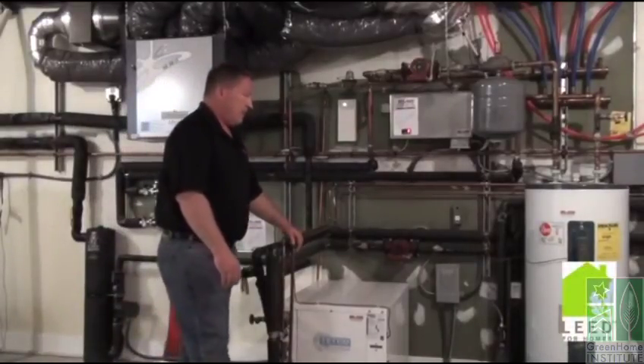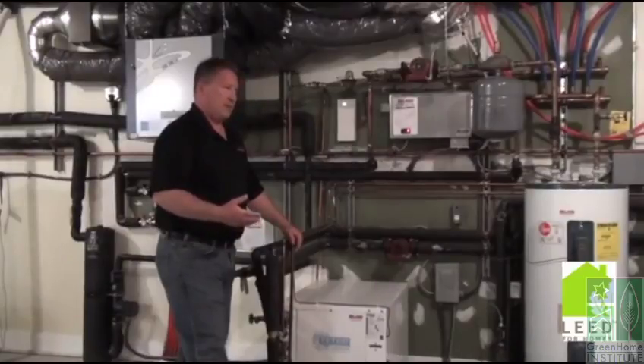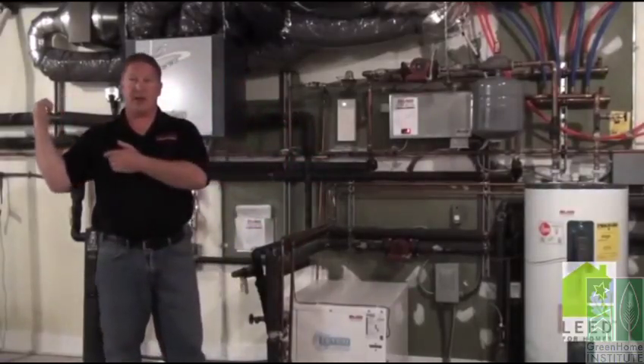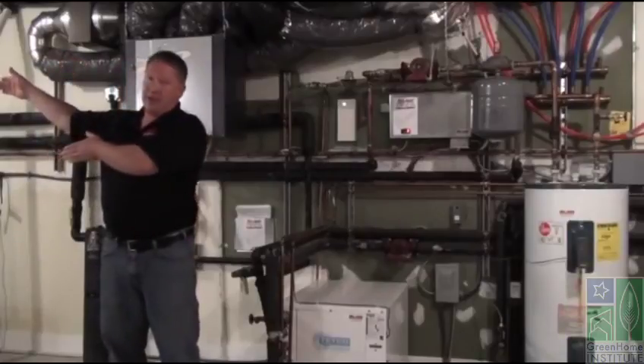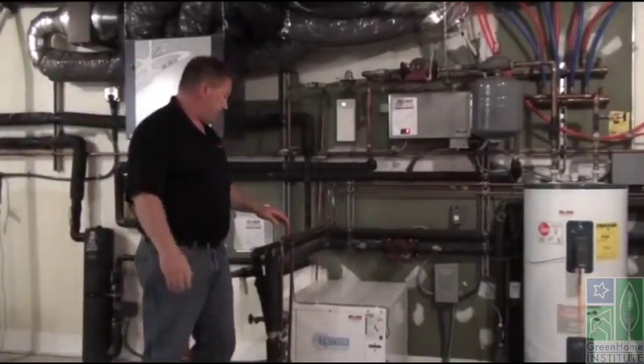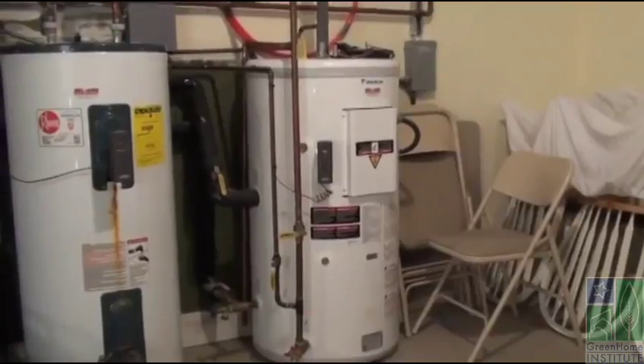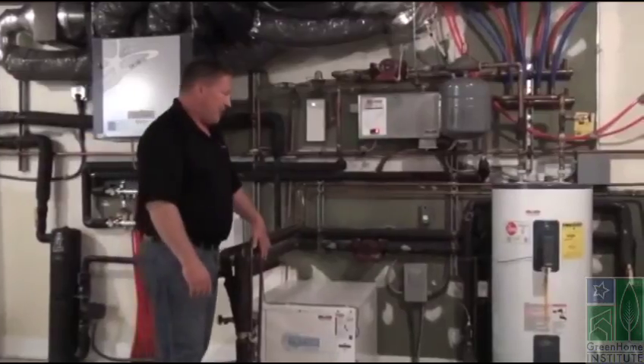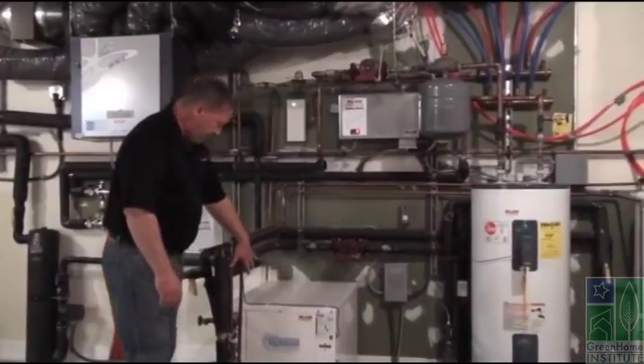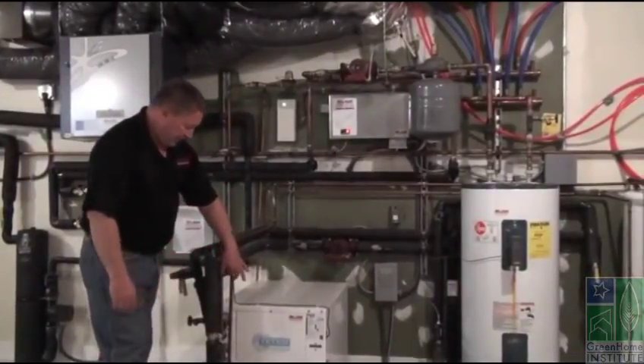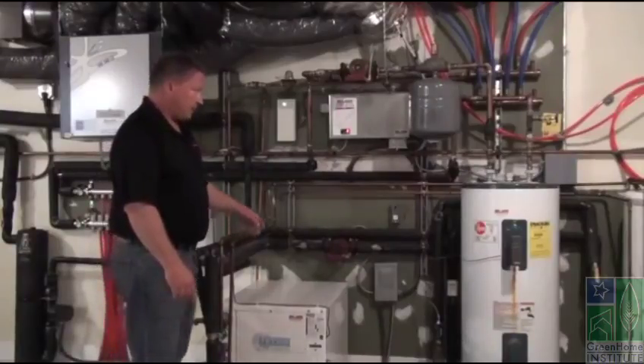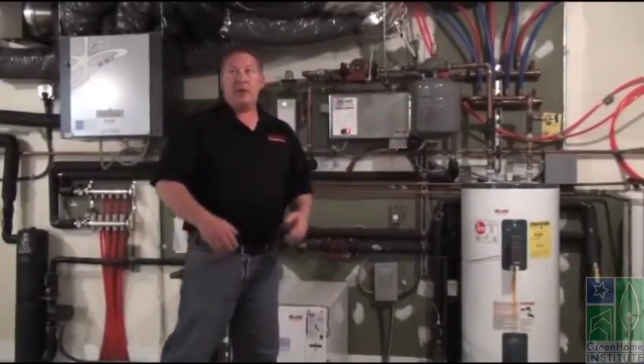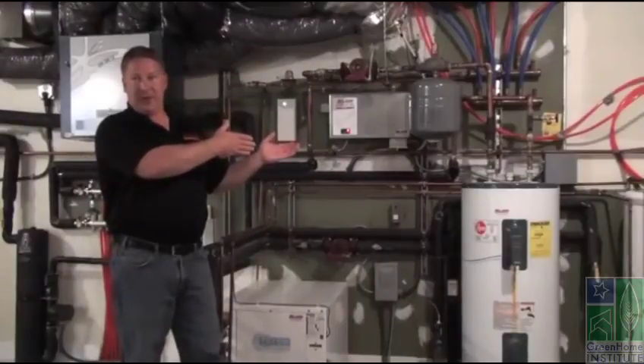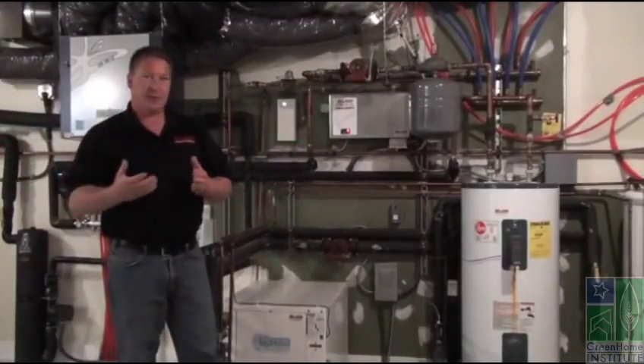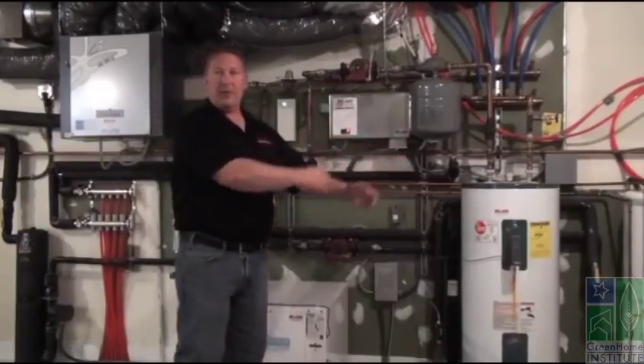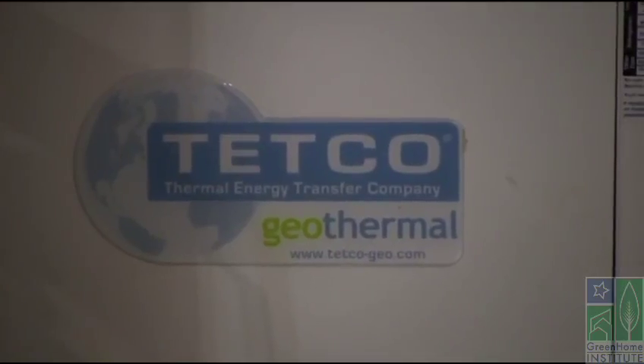There's also what's called a desuperheater. So when we're cooling, we have extra heat because we're taking heat out of the floor and dumping it outside. So as opposed to transferring that heat into the earth, we can actually transfer some of that heat into making domestic hot water. The desuperheater does that automatically. It has a separate pump inside the unit, a circulator pump, that circulates through these two small copper lines that then go into the domestic system. So the additional heat that we're removing from the space, instead of just bringing it outside, we're going to capture some of that heat and make hot water with it, which is pretty efficient.